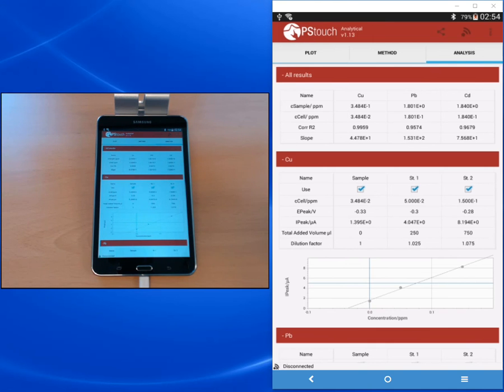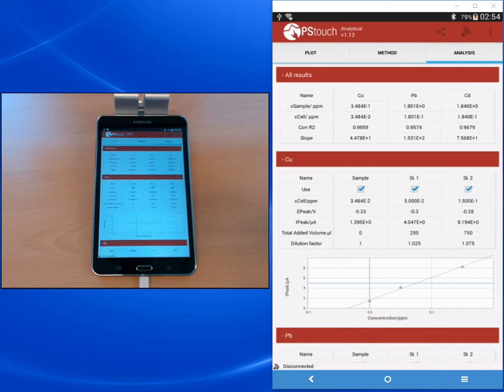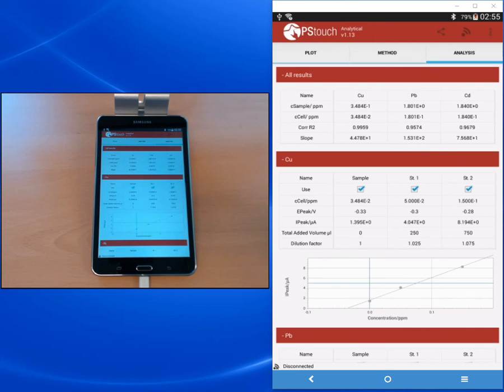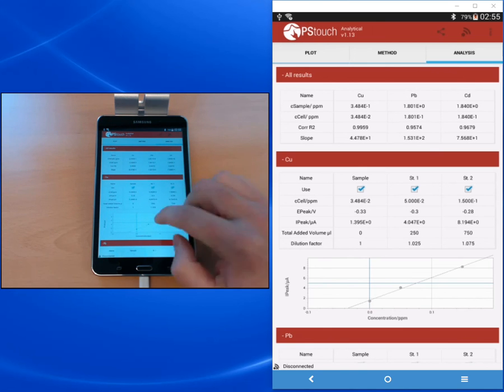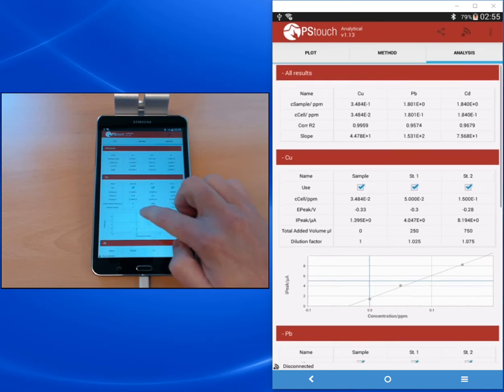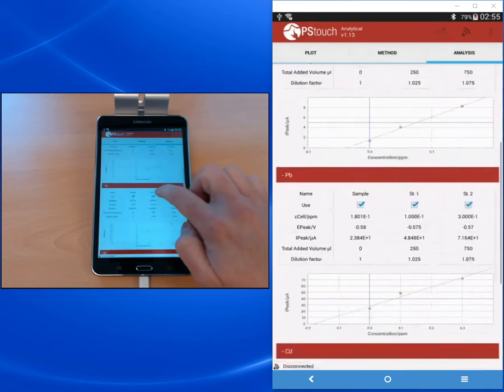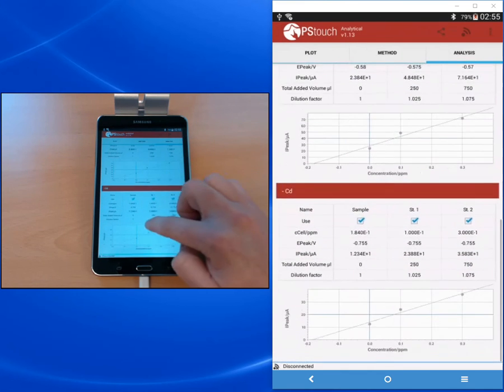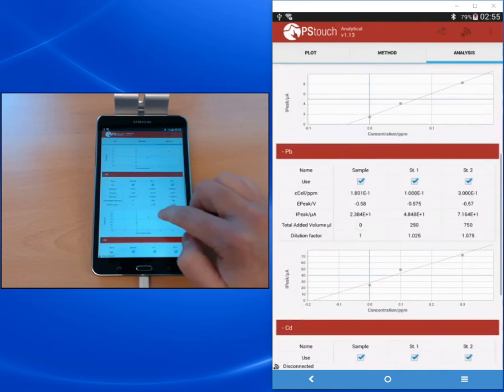The correlation coefficient R squared indicates how well the points that we measured are arranged on a line. A perfect line would deliver an R squared of 1, and the lower the value is, the further away it is from the perfect line. Below that you find the slope. The slope also represents the sensitivity of your method and sensor. Changes of the slope can be used as a quality control, so if the slope is significantly changing, especially if the sensitivity is dropping, you should change your sensor maybe. Below that you see all the results for the single analytes.